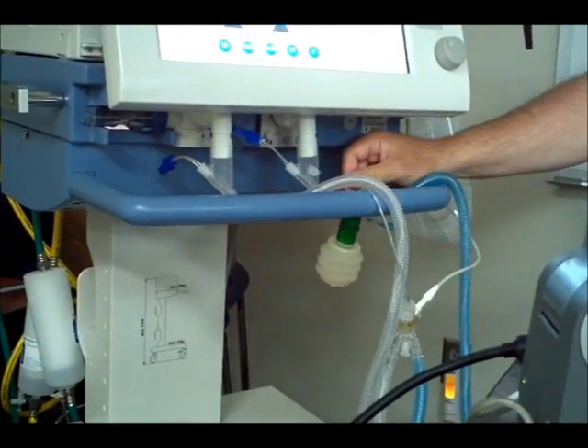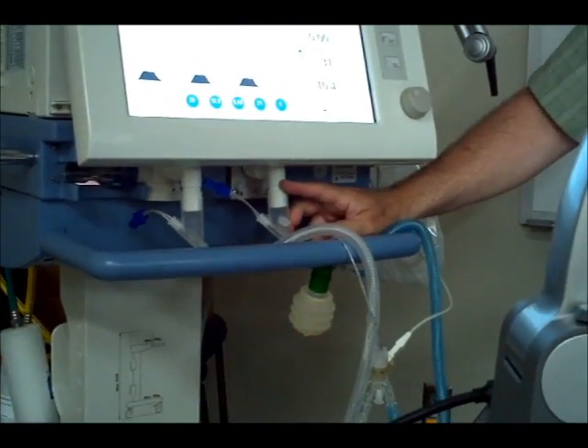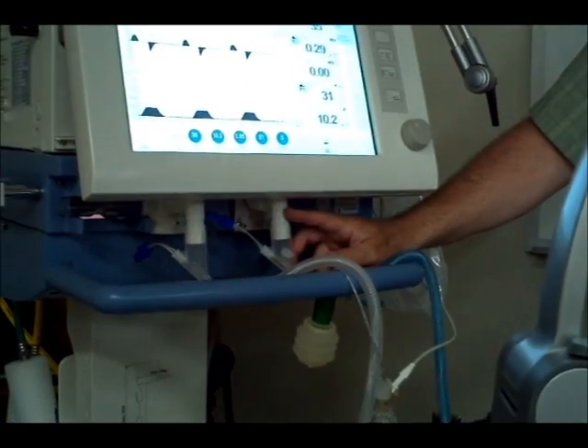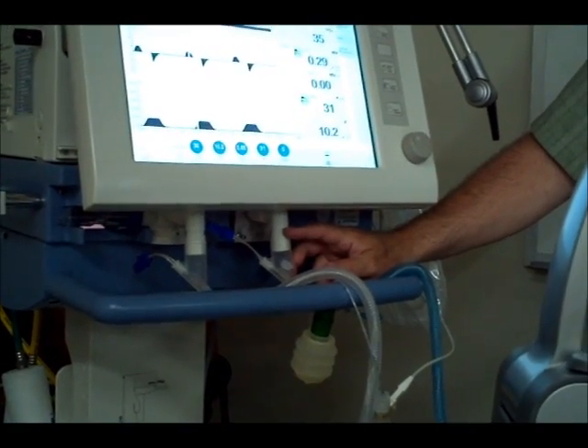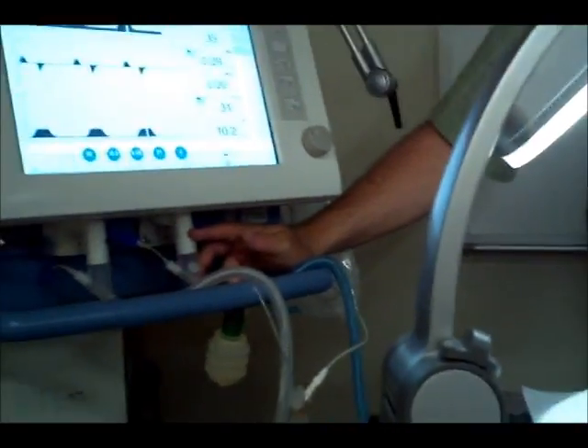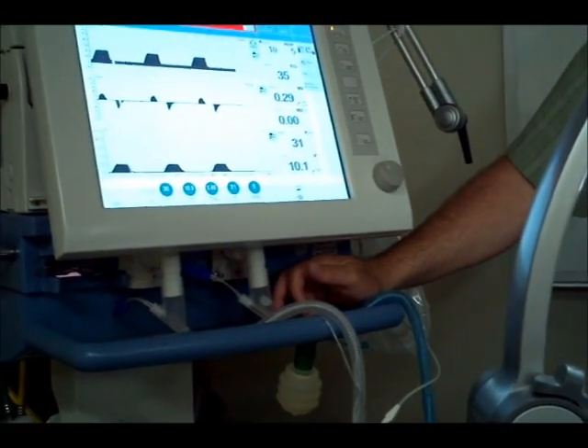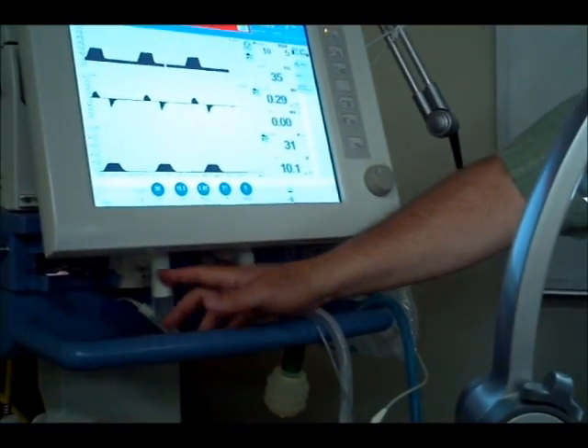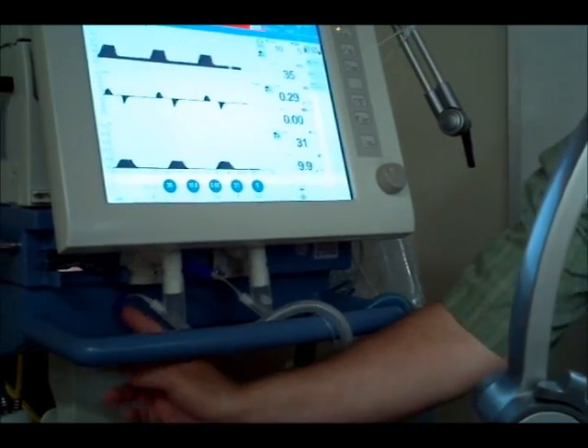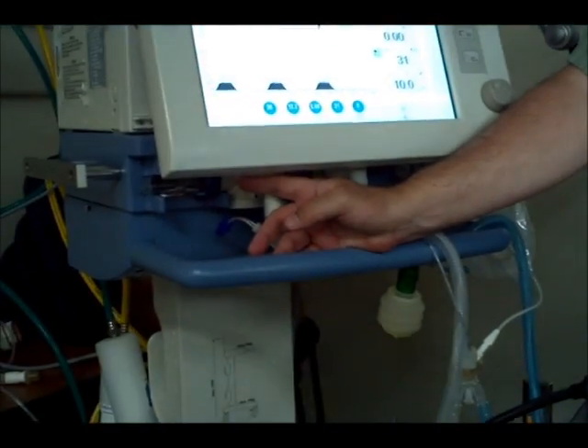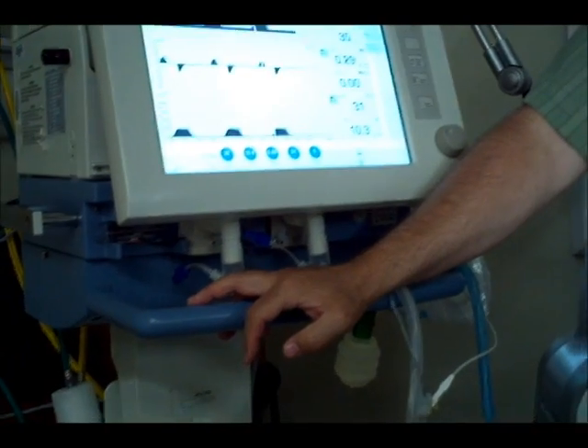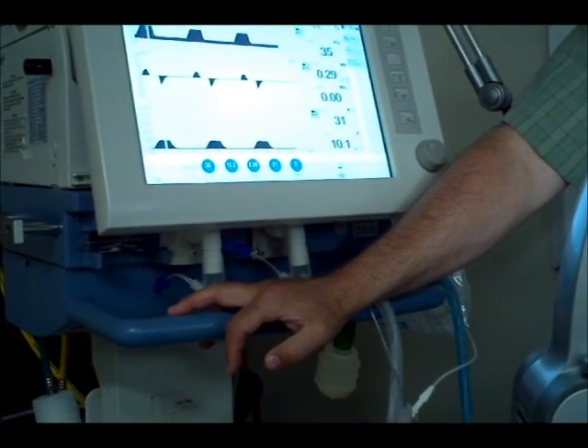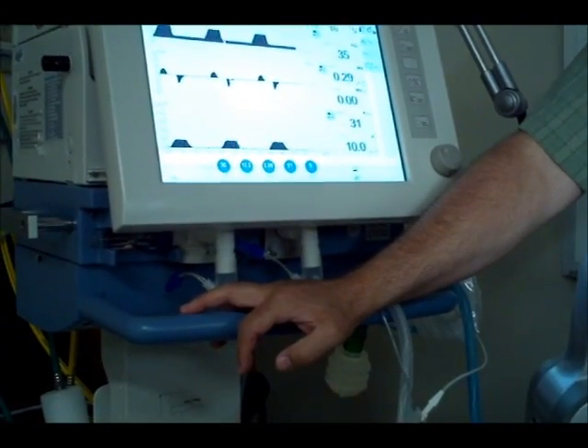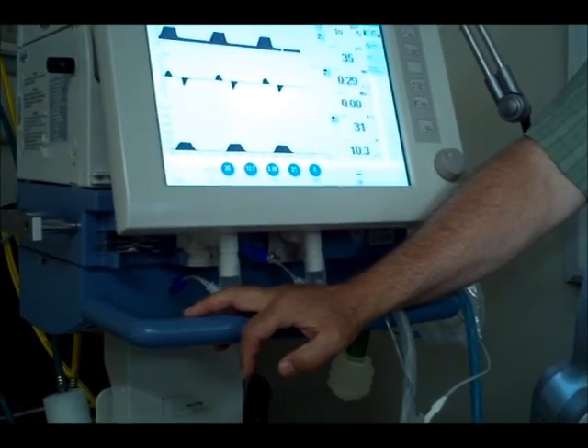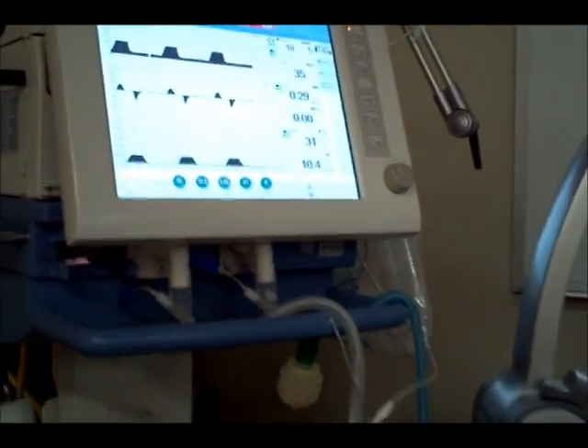Inspiratory tubing, again, having done the Babylog already, some of this will be fairly familiar for you. Inspiratory side is right here. Again, you can maybe go by the arrows, but sometimes these elbows get switched out, and you may find an inspiratory elbow on the expiratory side and vice versa. Probably the best way to do it is your expiratory side is over on the side with the exhalation valve and that expiratory flow sensor that I told you about. If you're good at memorizing which is on the right side and which is on the left side, then you can do it that way. Expiratory side is on the left as you look at the ventilator.